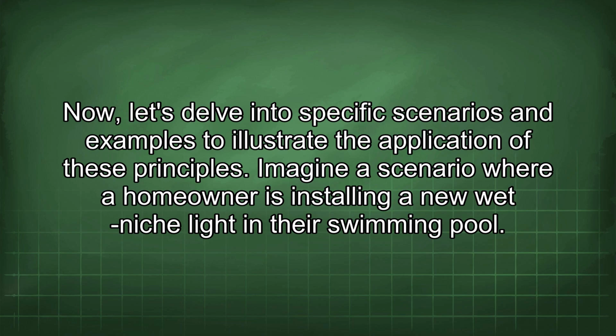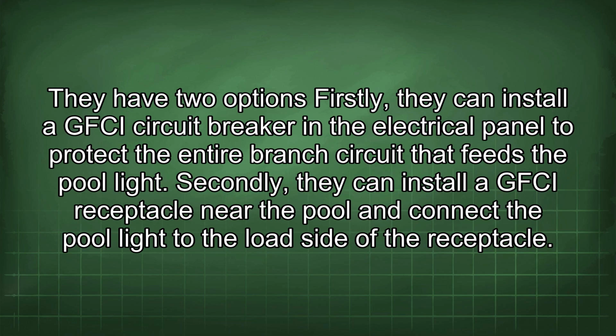Imagine a scenario where a homeowner is installing a new wet niche light in their swimming pool. They have two options. Firstly, they can install a GFCI circuit breaker in the electrical panel to protect the entire branch circuit that feeds the pool light. Secondly, they can install a GFCI receptacle near the pool and connect the pool light to the load side of the receptacle.